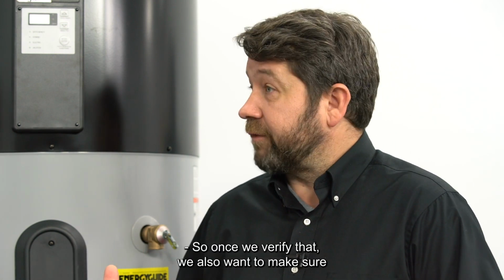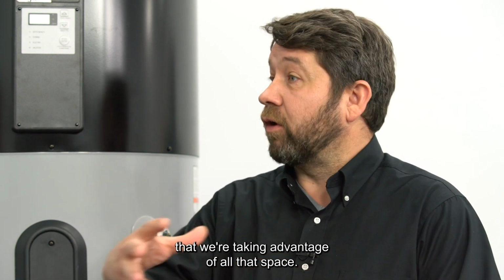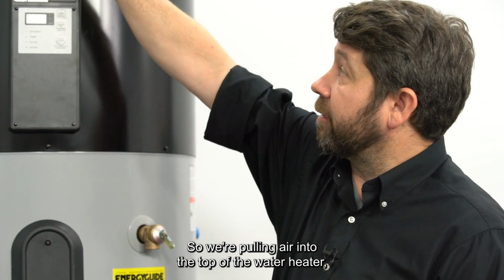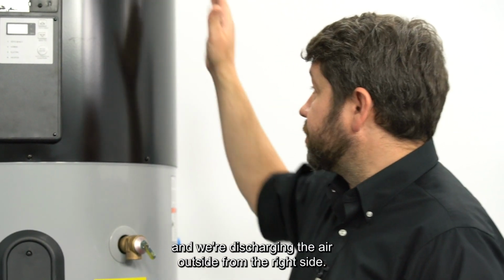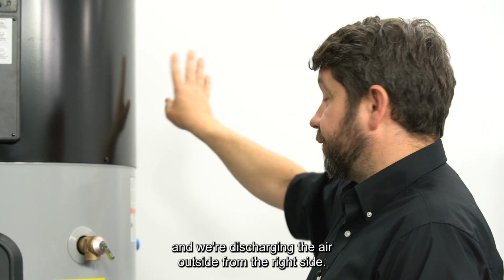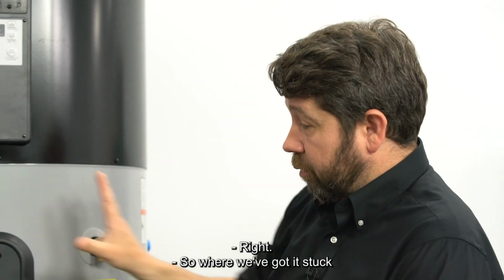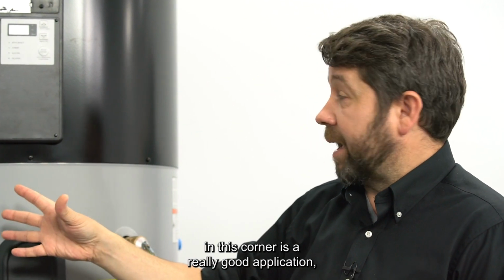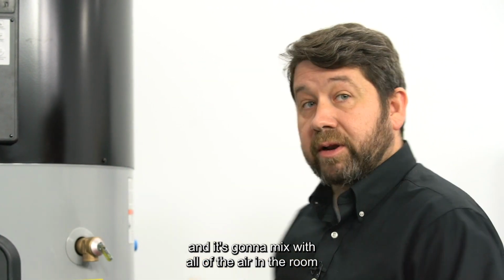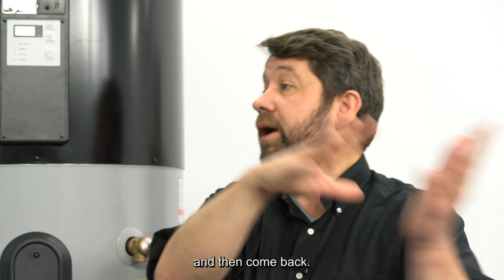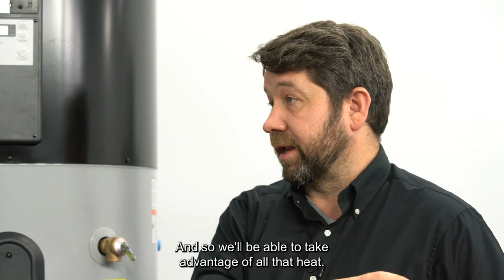Right. So once we've verified that, we also want to make sure that we're taking advantage of all of that space. So we're pulling air into the top of the water heater, and we're discharging the air outside from the right side. Right. So where we've got it stuck in this corner is a really good application, because we're going to blow this air out and it's going to mix with all of the air in the room and then come back, and so we'll be able to take advantage of all that heat.